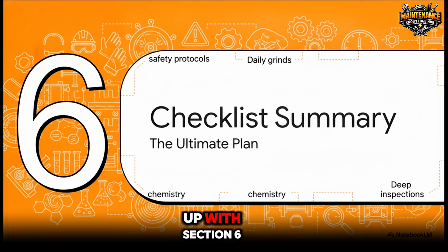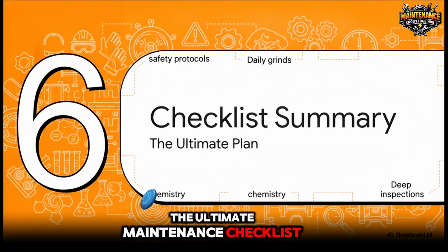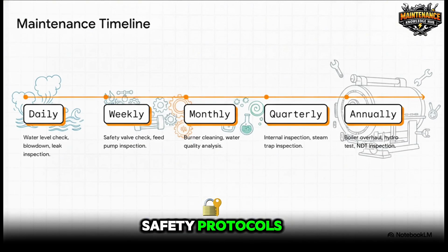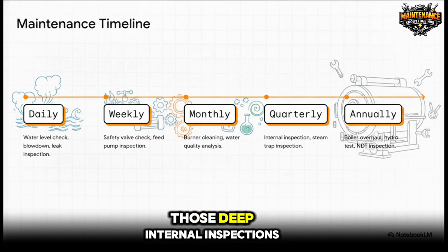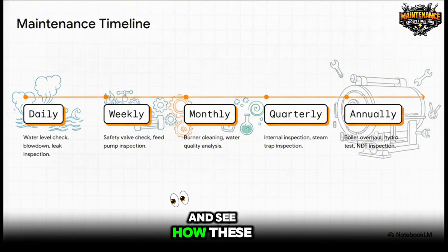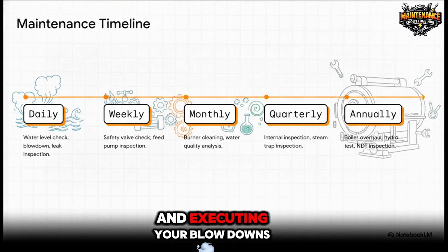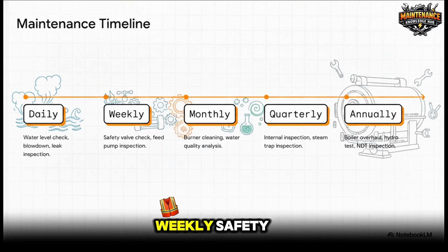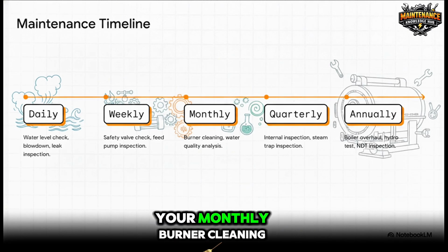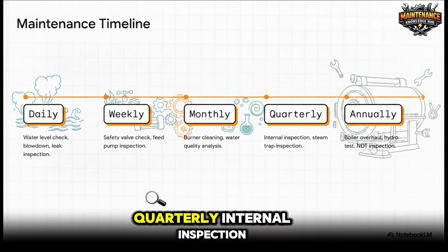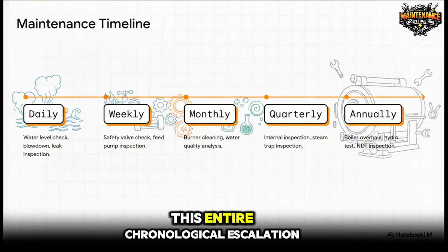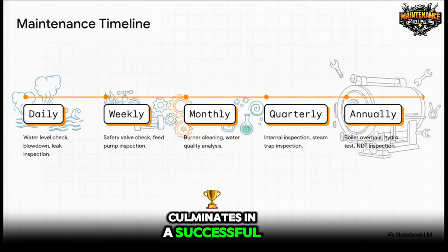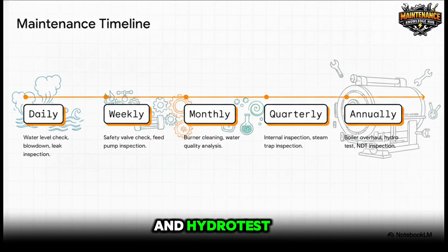Finally, let's wrap this up with Section 6, the Ultimate Maintenance Checklist. So, we've covered the strict safety protocols, the daily grinds, the water chemistry, and those deep internal inspections. Let's bring this all together and see how these routines build a compounding wall of defense. Every single day, you're verifying that water level and executing your blowdowns. That daily discipline ensures your weekly safety valve and feed pump checks go off without a hitch. Those weekly checks buy you the stability you need to perform your monthly burner cleaning and precise water analysis. The monthly rigor keeps your boiler clean enough for a smooth quarterly internal inspection. And all of this entire chronological escalation culminates in a successful, surprise-free annual overhaul and hydro test.